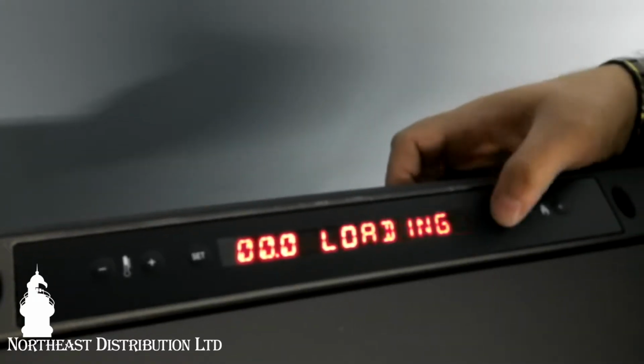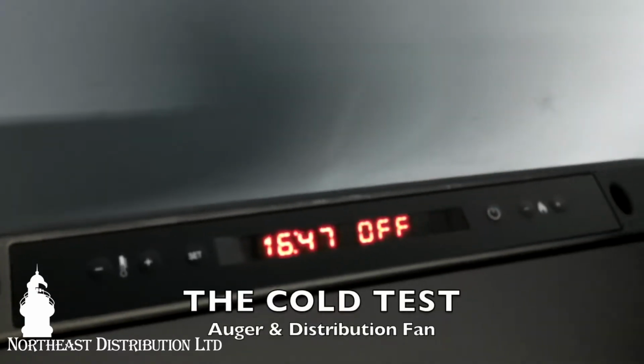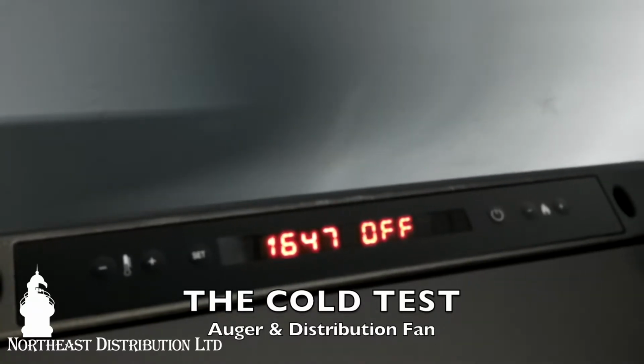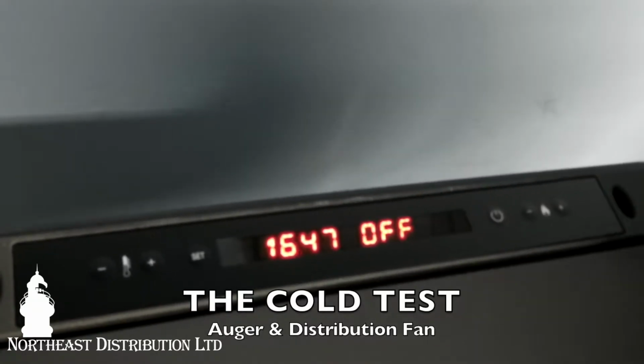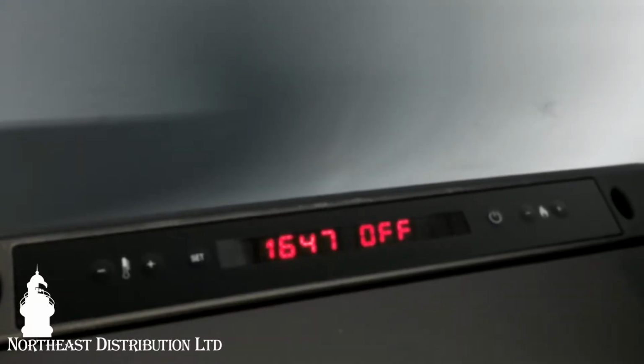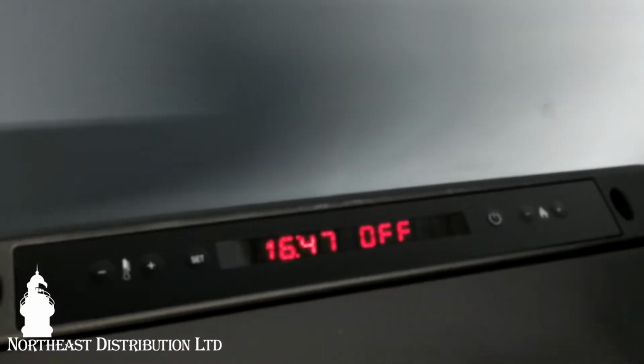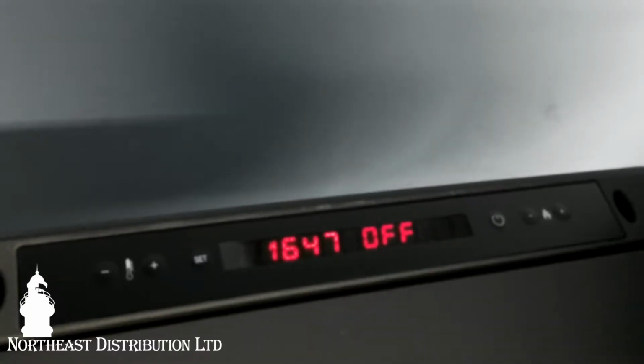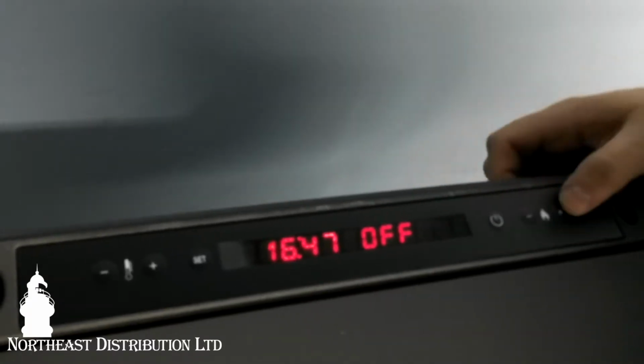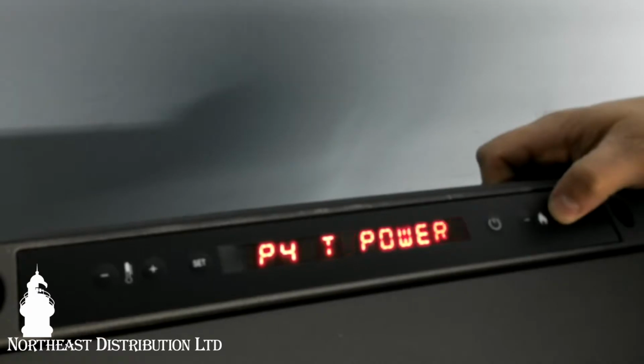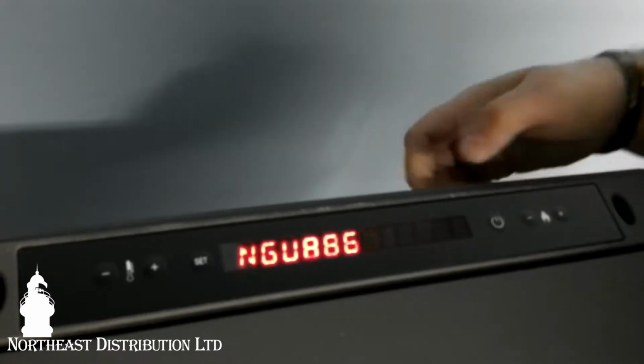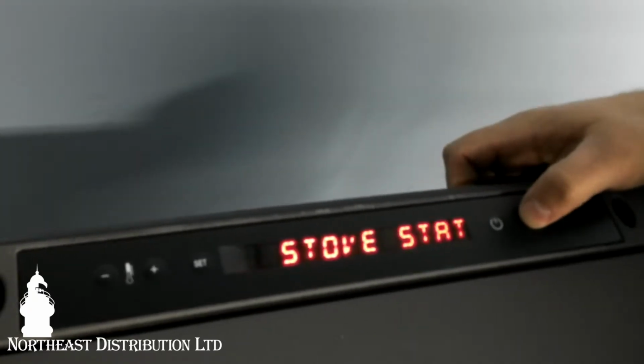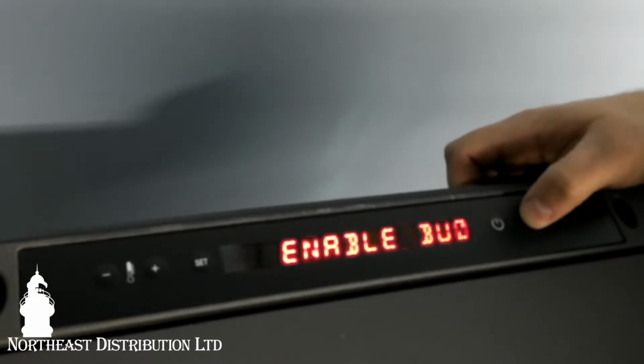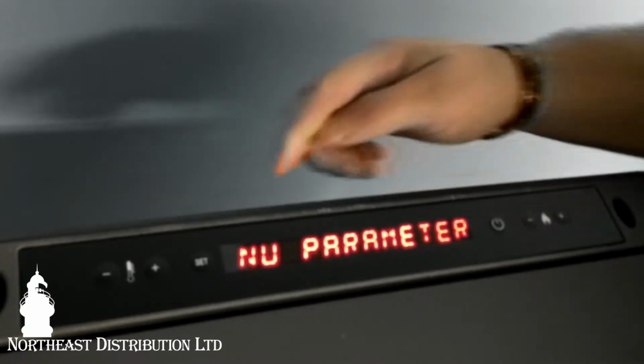The second thing I want to show you is how to do a cold test on this unit. I can run different parts of the pellet stove, again, without any fire, without anything in it. So we're going to test the auger and see if it spins, and we'll test the distribution fan and see if it works also. So again, we want to get into programming. Then we're going to scroll through till we see the word menu parameters. As we see here, we hit the word set.